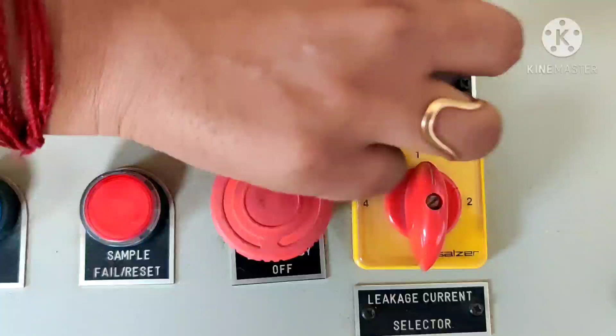Now, similar to our transformer oil experiment, once you have turned on the mains, you have to turn on the HT. Until you turn on the HT, the conversion from 230 volts to 50 kilovolt will not take place.